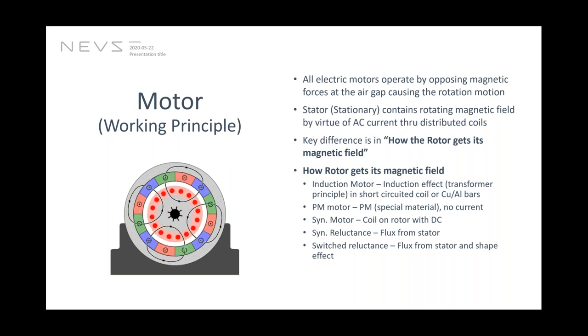The synchronous motor basically has a coil supplied through a commutator, not a commutator, but probably some brushes. A DC current is supplied into the coil, and it creates a static DC field which interacts with the rotating stator field. In the synchronous reluctance machine and switched reluctance machine, the field from the stator passes through the air gap to the rotor, and the interaction is due to the shape effect and the slots in the rotor that produces the interaction and the torque.